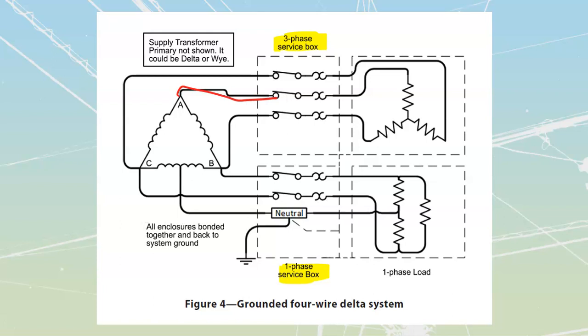What I'll see is two separate loads, or two separate boxes that are going to go off here. I'm going to have this B phase that is going to get split. Part of it's going to get sent into a single-phase service box. Part of the B phase is going to go to the 3-phase. Same with my C phase. Part of it's going to go to the 3-phase box for 3-phase loads. And the other part of C is going to go into my single-phase box over here, that I'm then going to be able to feed the single-phase loads out of. So we got lines over here. We got a neutral over here. We got this neutral point that is going to be the middle of this transformer. Once again, we're going to ground that neutral, and then we see that all of my bonded systems are connected together. This box connects to that box, connects to that box, connects all the way back through, etc.